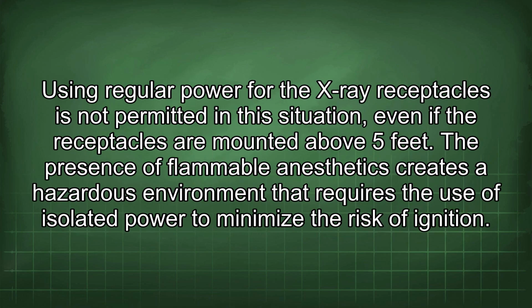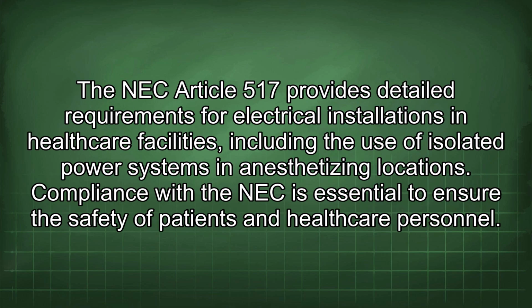Using regular power for the X-ray receptacles is not permitted in this situation, even if the receptacles are mounted above 5 feet. The presence of flammable anesthetics creates a hazardous environment that requires the use of isolated power to minimize the risk of ignition. The NEC Article 517 provides detailed requirements for electrical installations in healthcare facilities, including the use of isolated power systems in anesthetizing locations. Compliance with the NEC is essential to ensure the safety of patients and healthcare personnel.